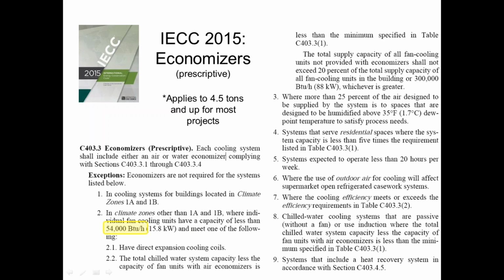It applies to all systems, right? So all fan cooling units. If I have a fan and I have a cooling coil, I have to do this. So that means if I put a residential split system, a furnace and an AC, in a commercial building, I have to do this. So 3 tons was making it pretty tough to do some of these things on a residential system in a commercial building.